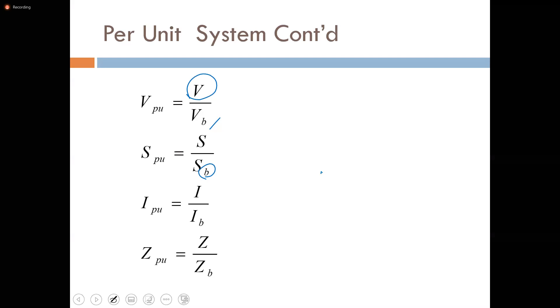So actual refers to the value of the quantity in the actual units, and the base quantity is also in the same units, which makes the per unit value dimensionless. Sometimes instead of per unit we use the percentage value, calculated by multiplying the per unit by 100. So if you have a per unit of 0.1, the percent value is 10%.